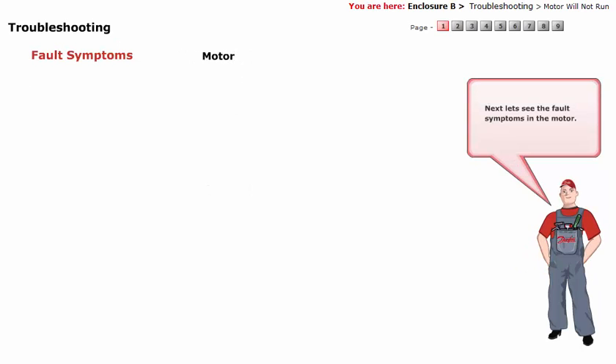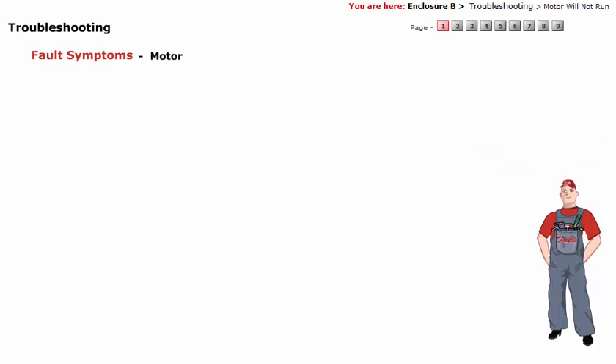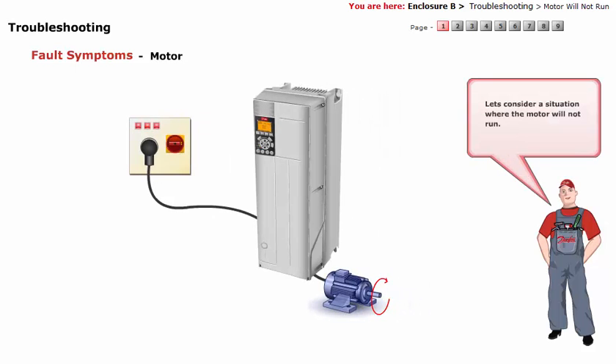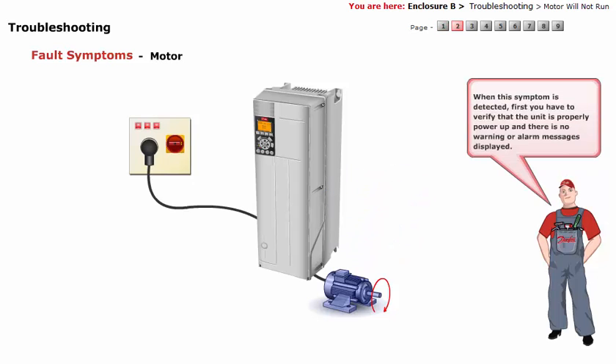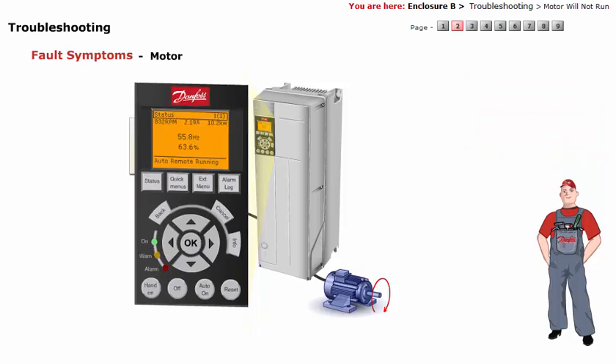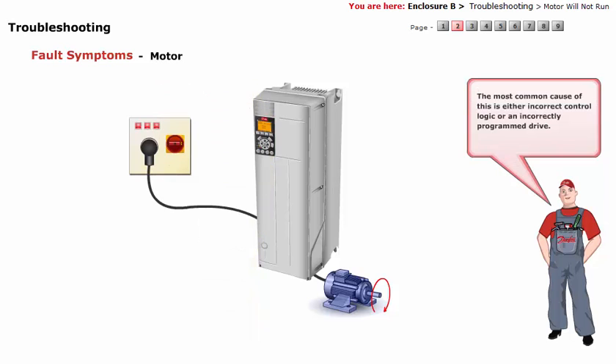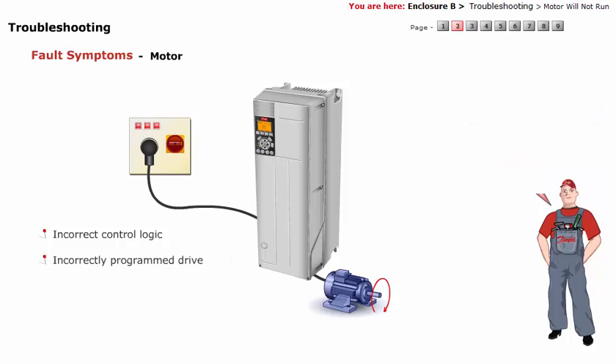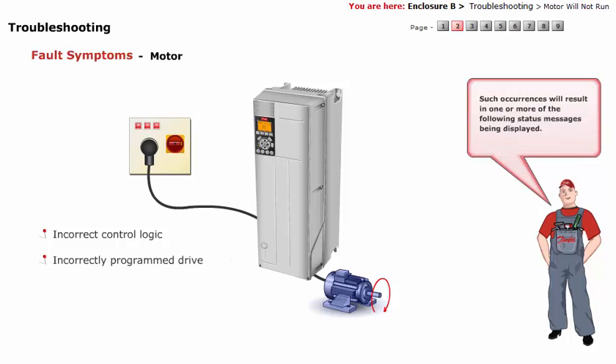Now let's see the fault symptoms in the motor. Consider a situation where the motor will not run. When this symptom is detected, first verify that the unit is properly powered up and that no warning or alarm message is displayed. The most common cause is either incorrect control logic or an incorrectly programmed drive. Such occurrences will result in one or more of the following status messages being displayed.